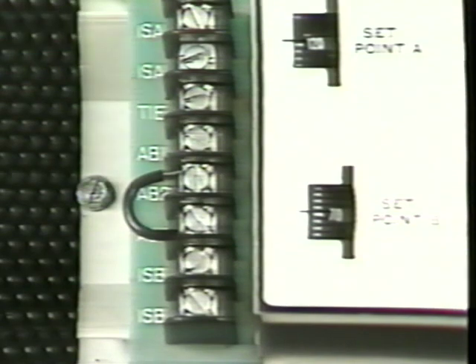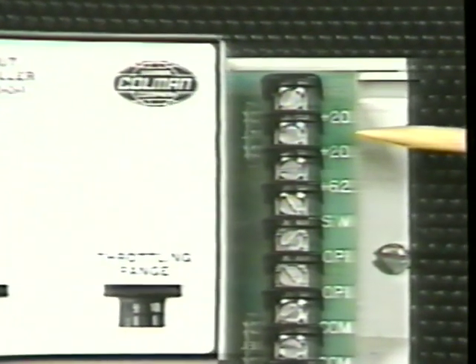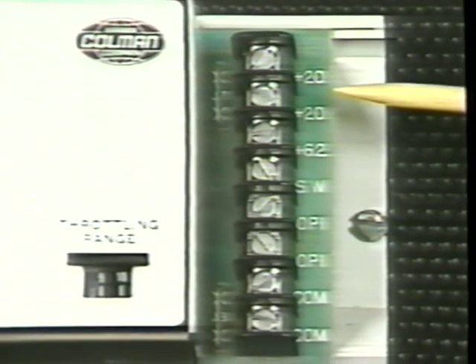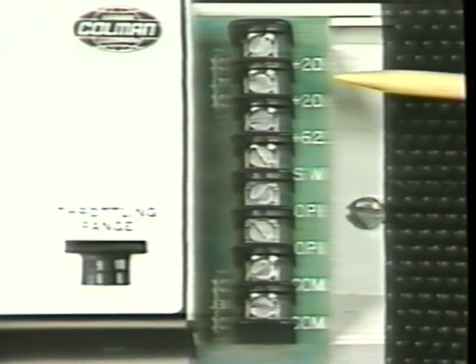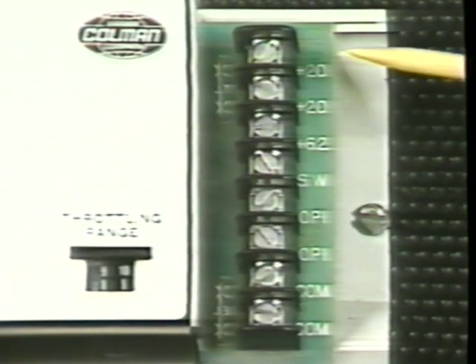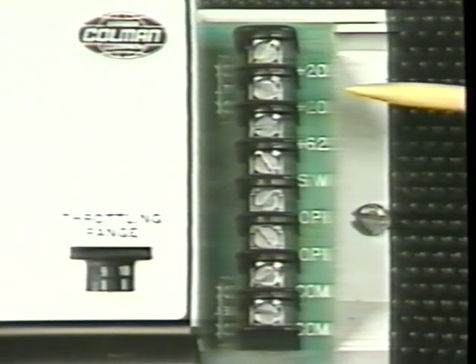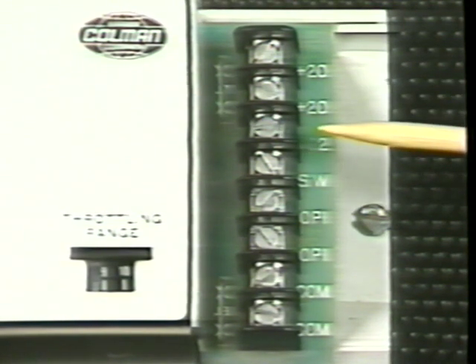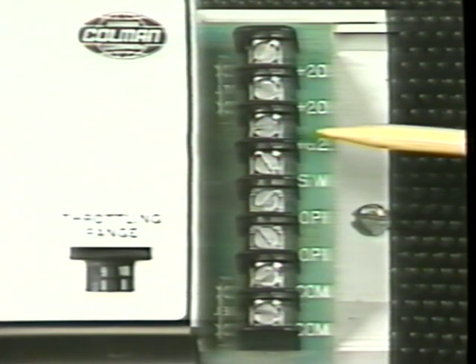Tie. This is a non-functional terminal. +20. This is a pair of identical power input terminals. The CP8102 requires 20 volts DC at 23 milliamps to operate. Either terminal can be used, with the power source usually a System 8000 controlled device. 6.2. This is a power output terminal used to power remote set point adjusters or external bridges. It's rated at +6.2 volts DC at 7 milliamps.